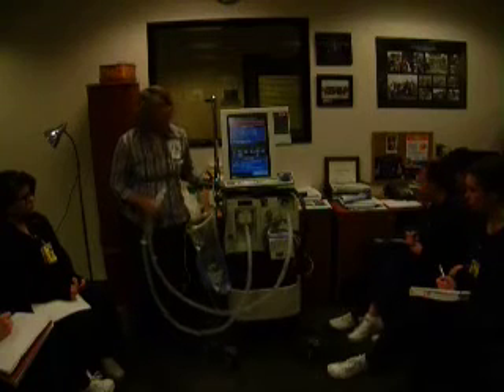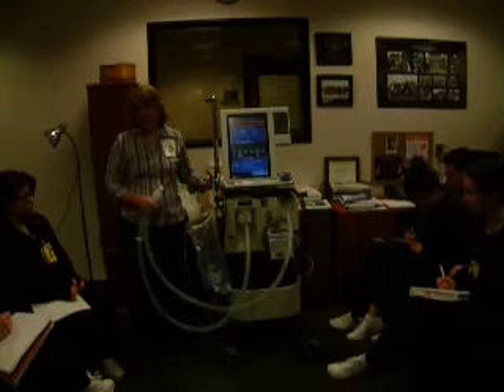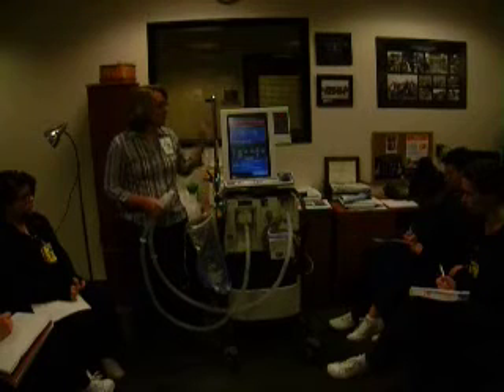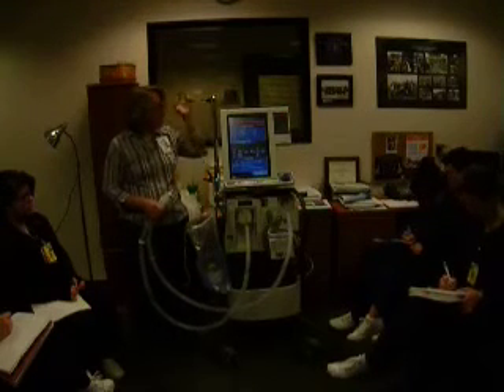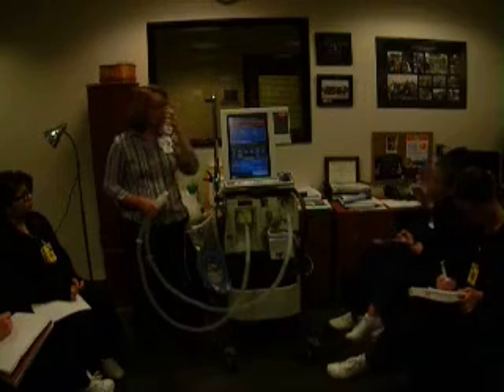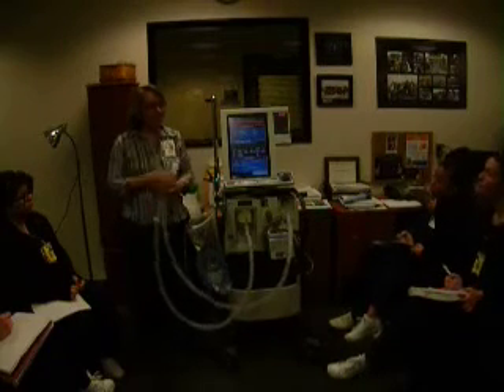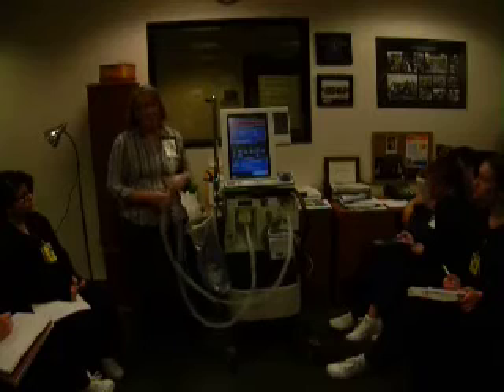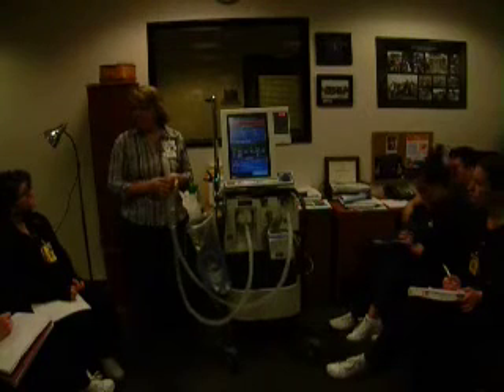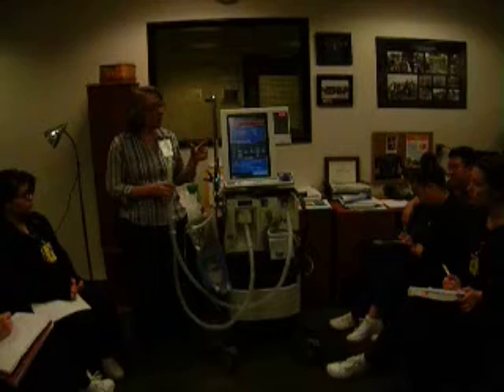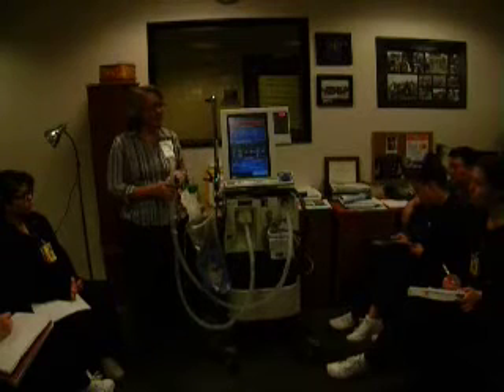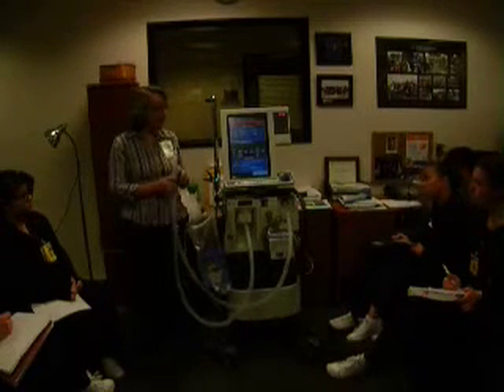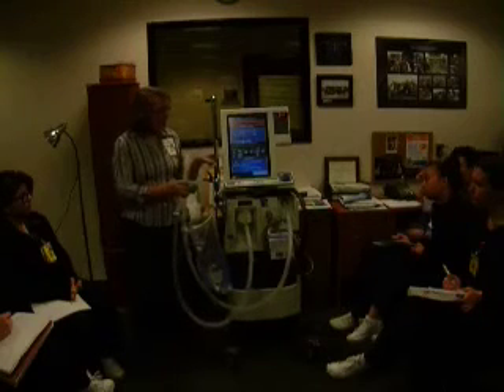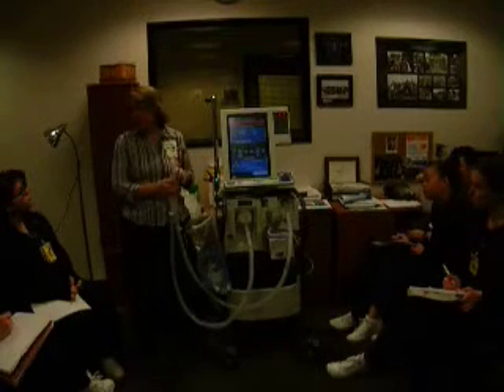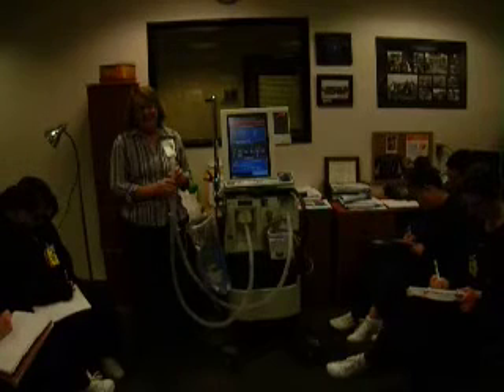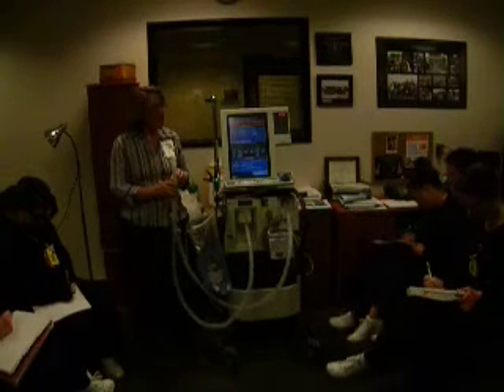So to do a calibration on this ventilator, all ventilators have some kind of calibration procedure. Some of them, it's computerized and it will tell you exactly what you do. The Galileo, it's not, and it's the old-fashioned way. In the old days, we used to just do manual calibration. The calibrations are safety checks to make sure that the ventilator's working, that it's done between patients or when you think there's a problem. Sometimes you'll actually do one in the room. It doesn't happen very often, but every once in a while you will. This PB840, the calibration test is called the SST. That stands for the short self-test.